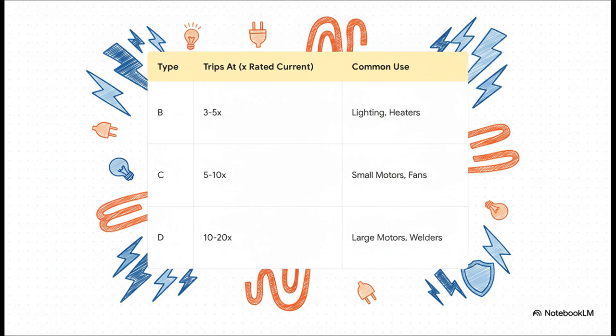A type C is a bit more forgiving. It's for things with small motors, like fans or a fridge, that have a tiny power surge when they kick on. It waits until the current is 5 to 10 times the rating. And then you have the type D, which is the real heavy hitter for industrial stuff like huge motors that have a massive power draw when they first start up. It won't trip until the current is 10 to 20 times the rating.